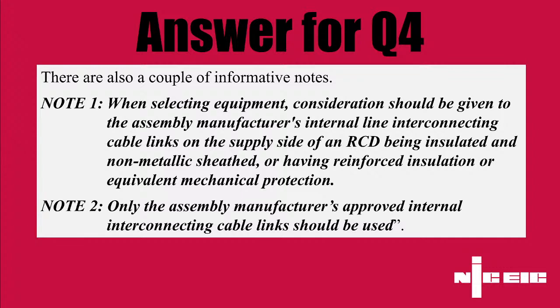Yeah, I always used to do it on the continuation page, Sam. For the first supply, I'll make a note on the installation cert. Say, please see continuation sheet for additional detail or other supply details. I'll list it on there. It's all about recording it and documenting it on the installation cert. To be fair, you want to capture as much information as possible, because then it also shows that you've done your due diligence and you've checked both sides. Basically, you can still meet fault current protection on either side. So yeah, absolutely.